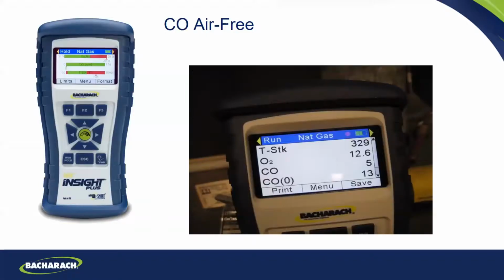You're going to notice on your analyzer you have CO air-free. Some of you may have CO and 0, meaning 0% oxygen. Some of you may have COAF, that would be air-free. Some may have COU, meaning CO undiluted. They're all saying the same thing. The industry is saying you can add more excess air and your CO readings go down, but you still have all those same molecules of CO. You're just diluting it. So they want something that takes you back to a base point, and that's CO air-free. CO air-free is just taking the oxygen out of the equation.